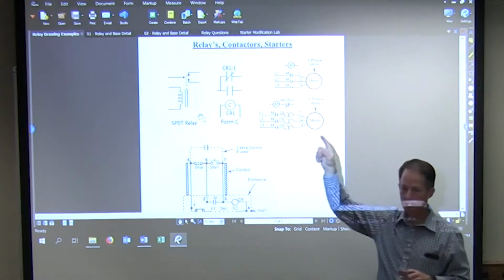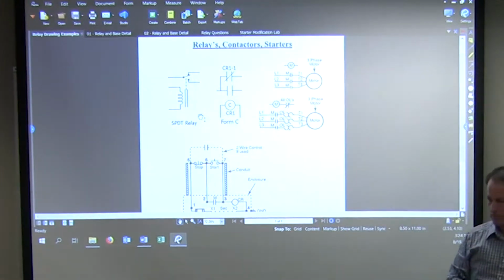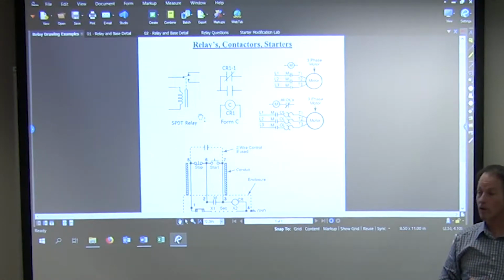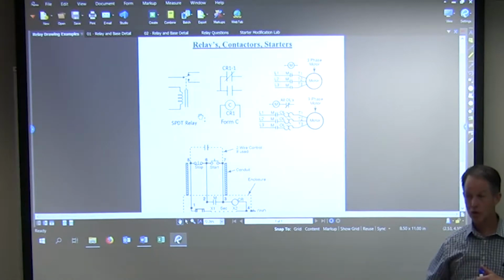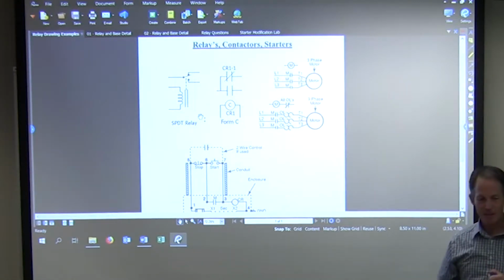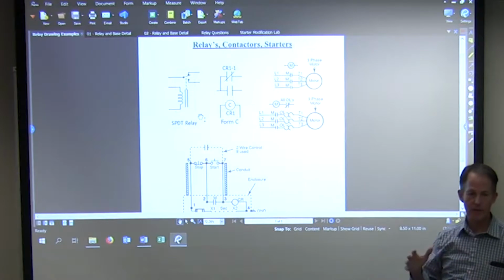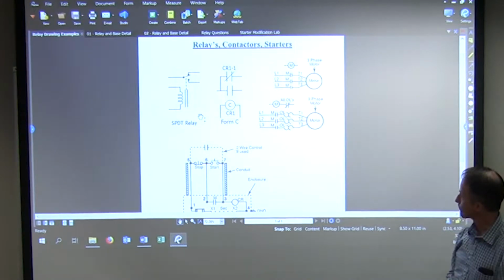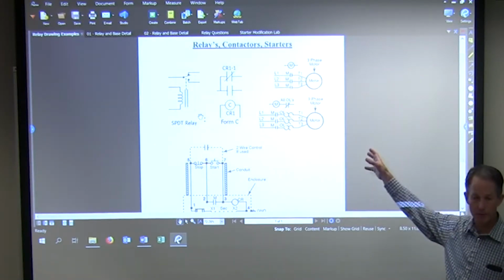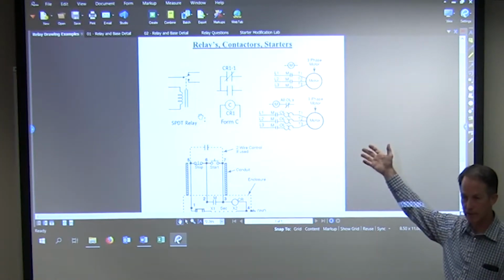So do overloads protect people? No, because you can still get several cycles before it opens up. They're not designed to protect me or you, okay? Have you ever touched an old motor that has a zap to it on the case? You shouldn't, but remember that tingle, you touch them and you're like whoa. That could kill you. The overloads will probably never trip in that case. So they're not designed for that, that's not the function of an overload, it's to protect the motor, the windings of the motor. Any questions or comments about motors, overloads, or contactors, at least to this point?